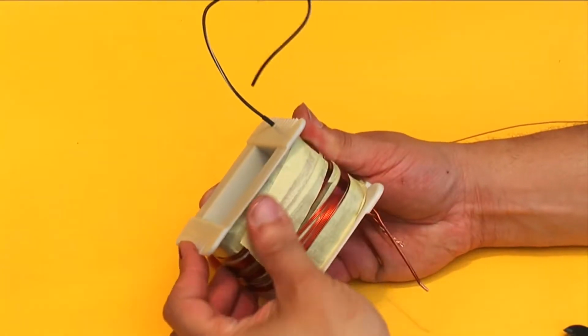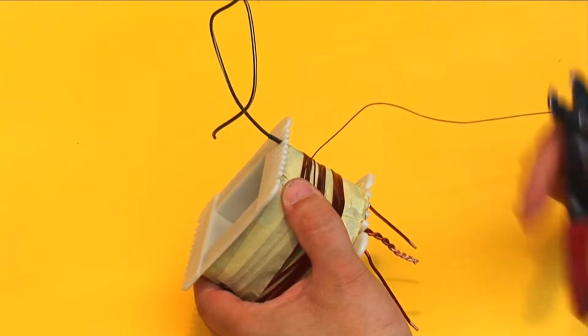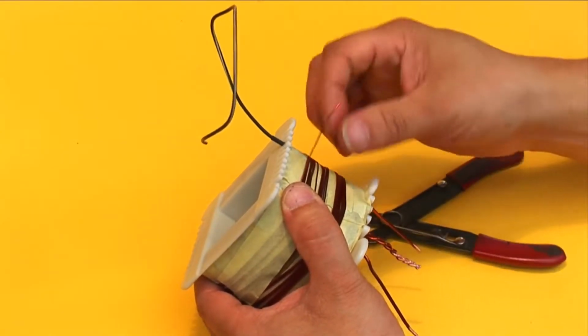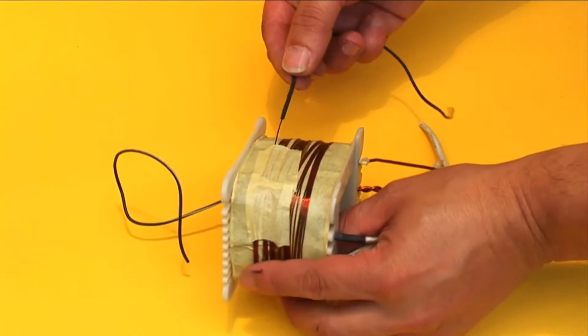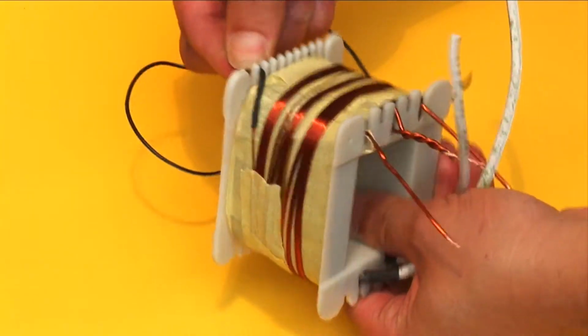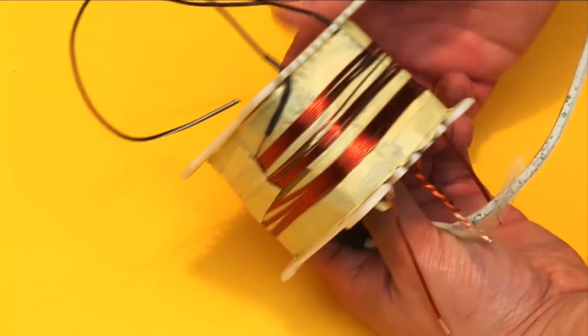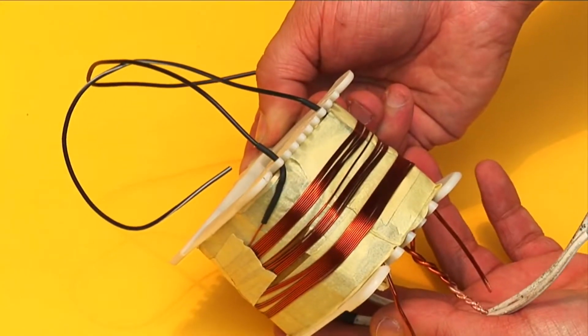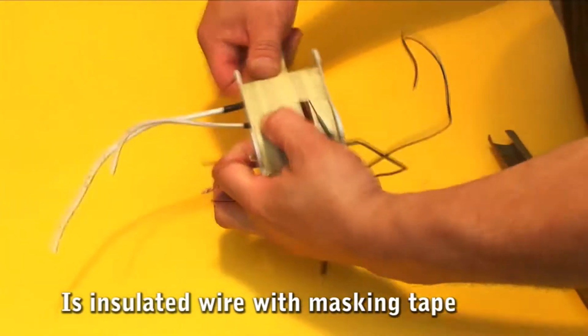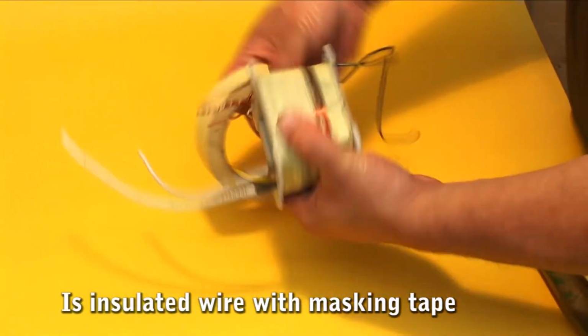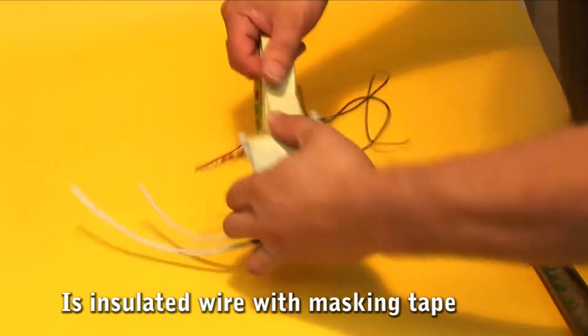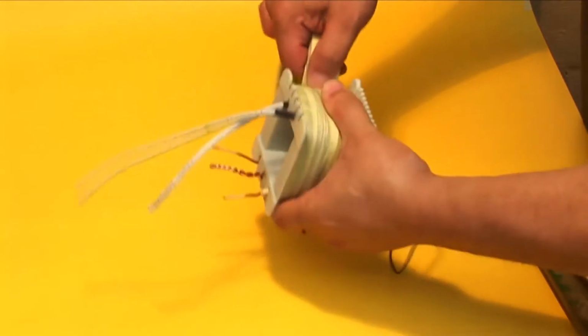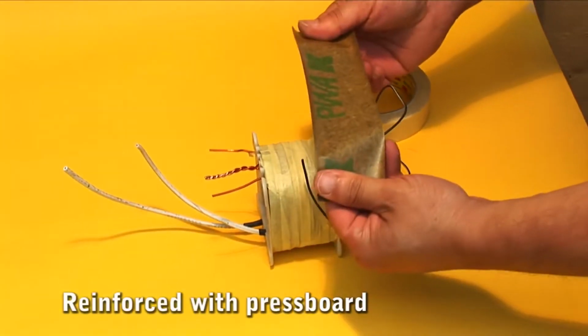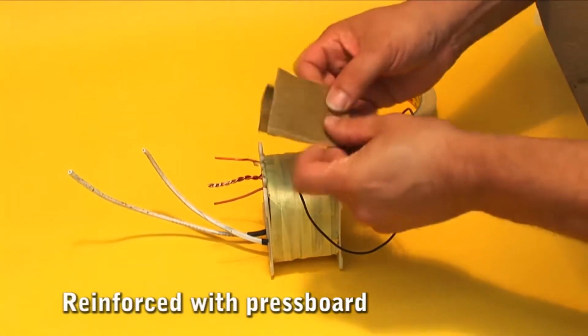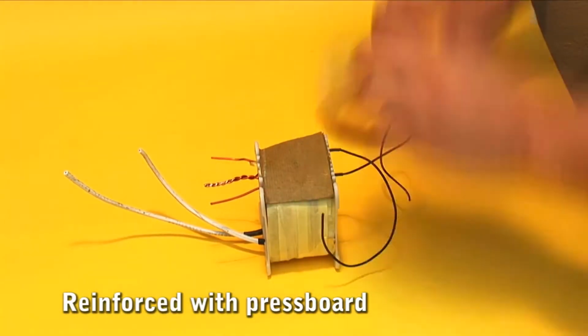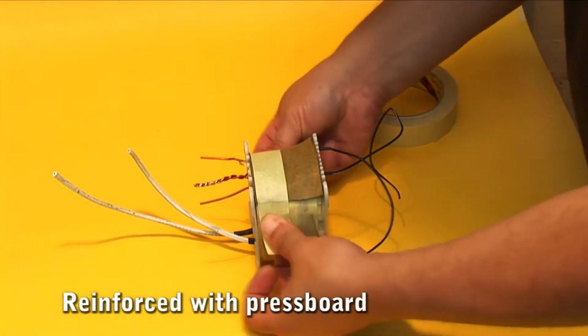At the end of winding the turns of wire for the additional winding, weld the tip to a plastic-coated wire. Remember to sand the tip of the wire. Weld it to the cable and insulate with heat-shrink insulator. The transformer is then covered with tape again, insulating the additional winding. Then, with a piece of waxed paper or pressboard, we straighten the part where the wires join the main secondary winding, with the output wire.